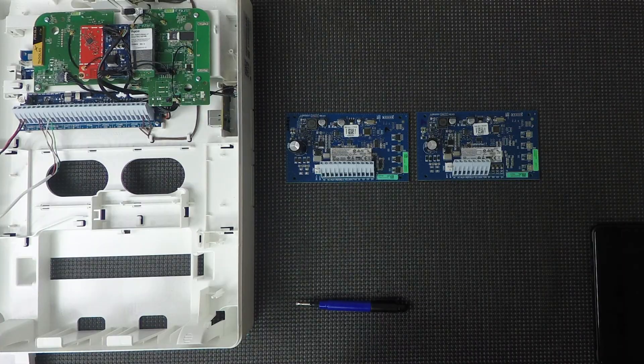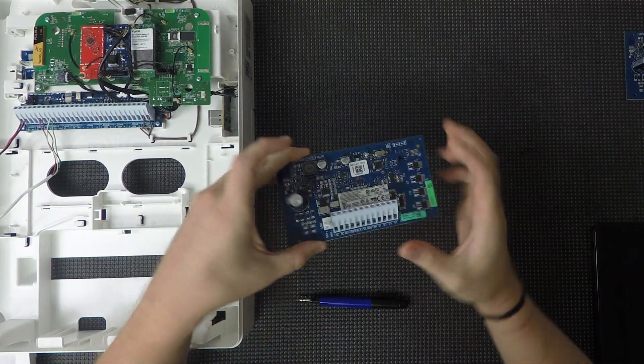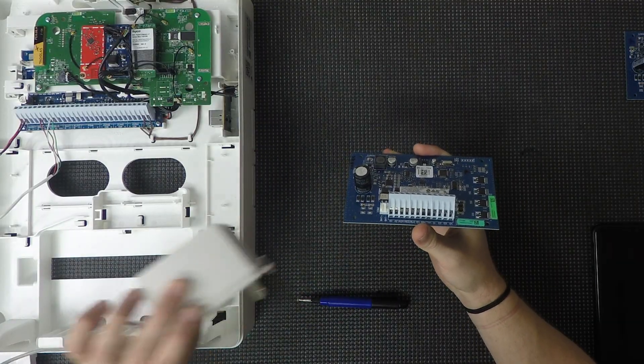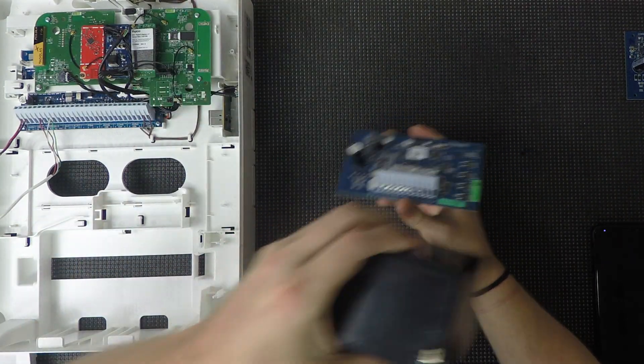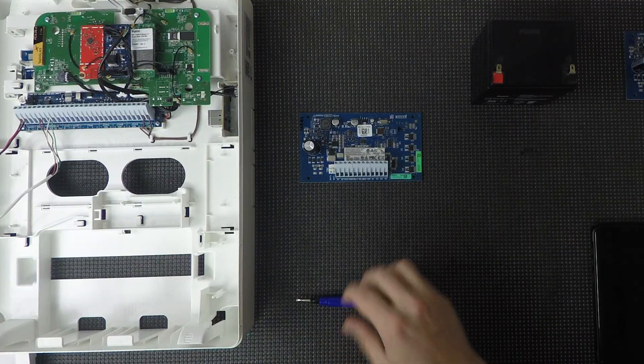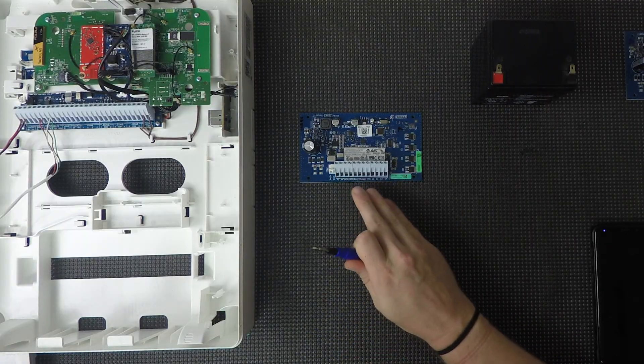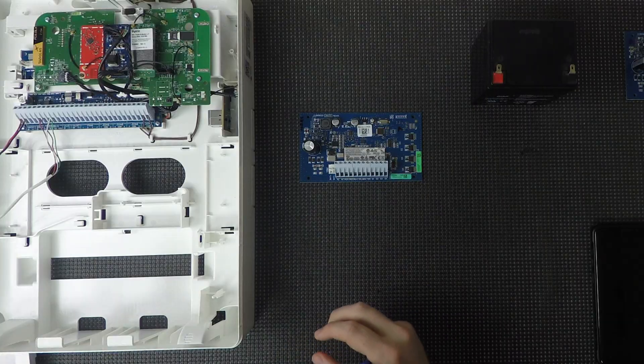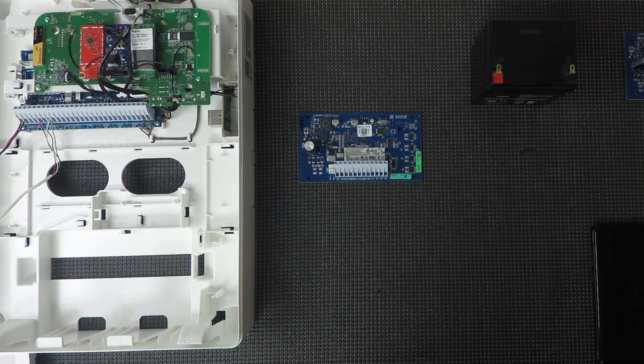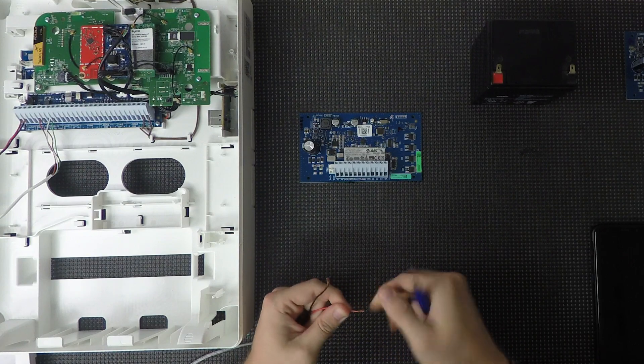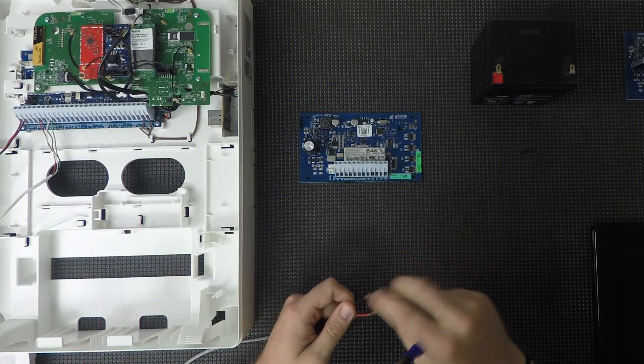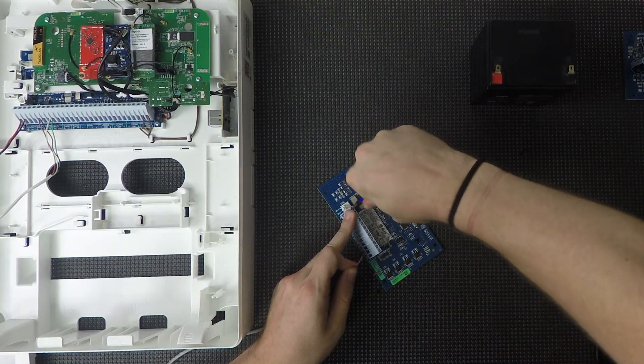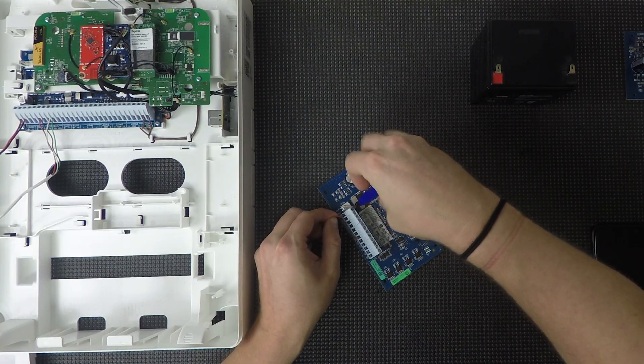So moving on, I'll go ahead and talk about how these would be installed. One of the most important things to remember when purchasing one of these, though, is that you need an additional transformer and you need an additional battery for the power supply. So I have both here. So we're going to go ahead and hook those up. So that would be the first thing you do. And then you can connect it to your system from there. Now, one thing to remember, once you hook up the AC, don't actually plug it into power. I have a power strip here that I'm using so I can get away with plugging it in before I actually turn the power strip on. However, in most cases, you can hook up your wiring, hook up the transformer, just don't plug it in until you are ready to completely boot up the system and get everything going. So, first thing you're going to do, just take your two AC terminals here. These would be the two on the left. And connect your two wires to the AC terminals.